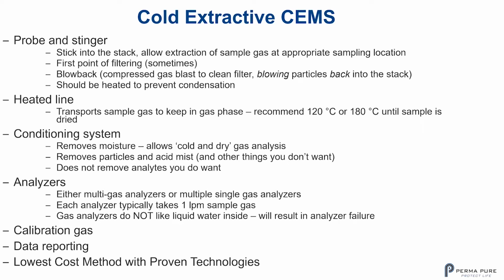they can create all kinds of havoc down the line because they're very acidic and very sticky. Then after your heated line, you have your sample conditioning system that removes the moisture, which allows the cold and dry gas analysis. It also removes particles and acid mists and other things you don't want. And it should not remove the analytes that you do want.